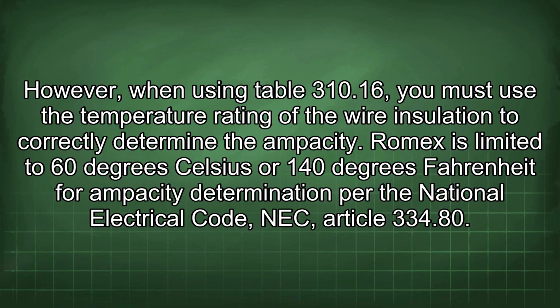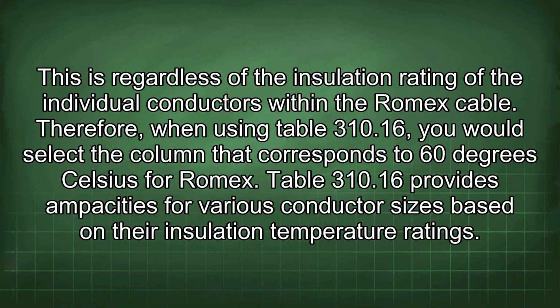Article 334.80. This is regardless of the insulation rating of the individual conductors within the Romex cable. Therefore, when using table 310.16, you would select the column that corresponds to 60 degrees Celsius for Romex.